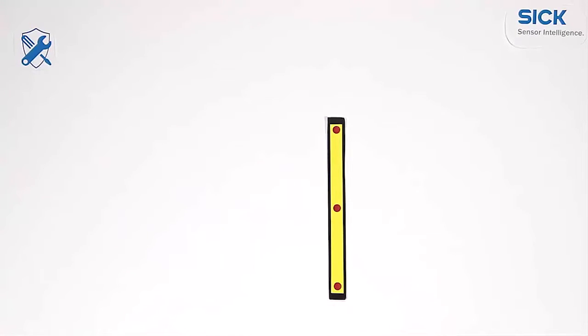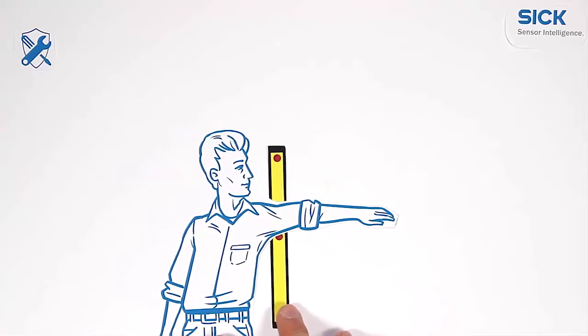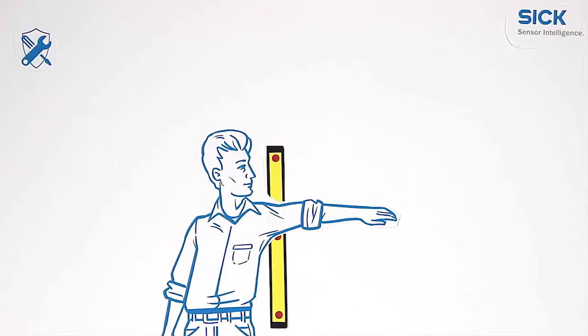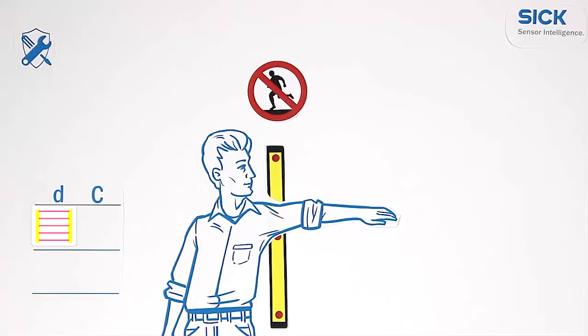Using a multi-beam system, a whole arm can reach through the light beams. Only bodies can be detected. For that reason, c is significantly larger: 850 mm.